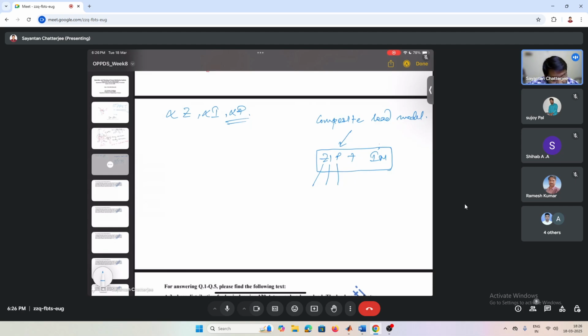My point was to emphasize this induction motor type, because as was asked, power load might be leading - but that won't be the case in the Indian context, or in most contexts. System loads are mostly defined by induction motors since industries mostly run on induction machines. Around 65 to 70% of loadings are defined by IM, induction machine, and these are mostly the loads we use. From the ZIP model, we may find a few equipment following these models, except for pumps and similar things which fall under induction machines.